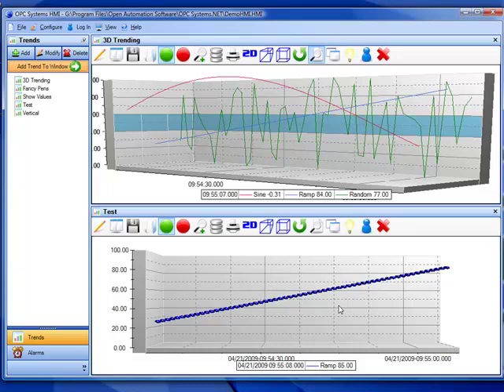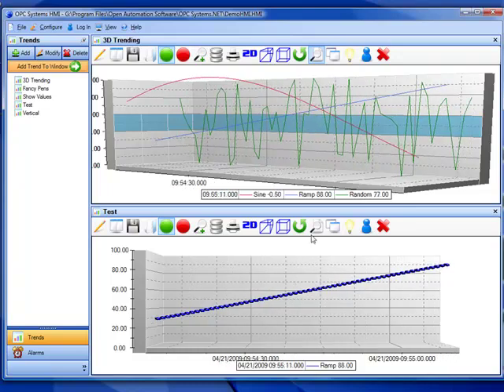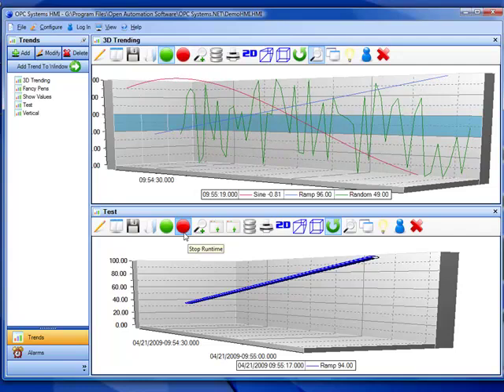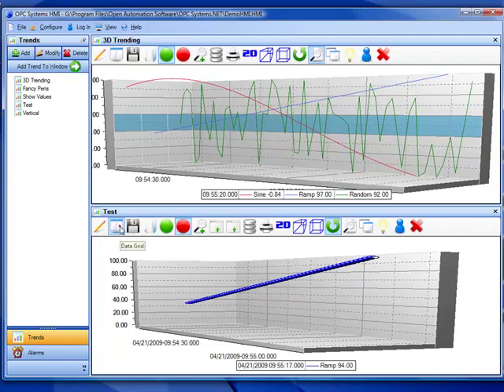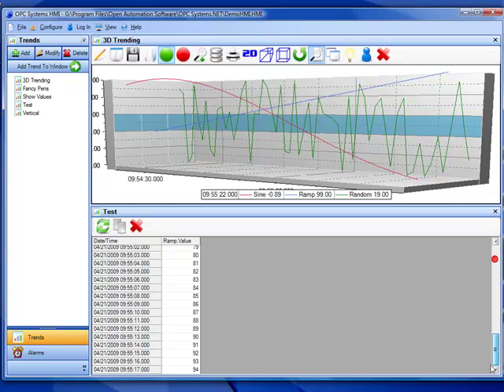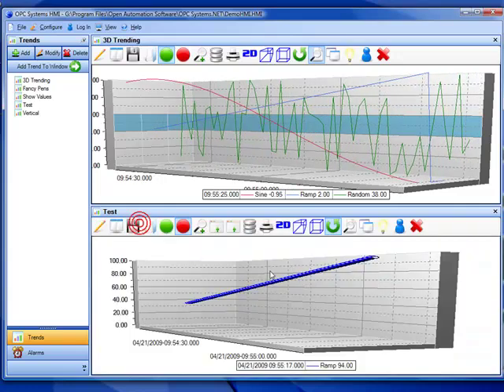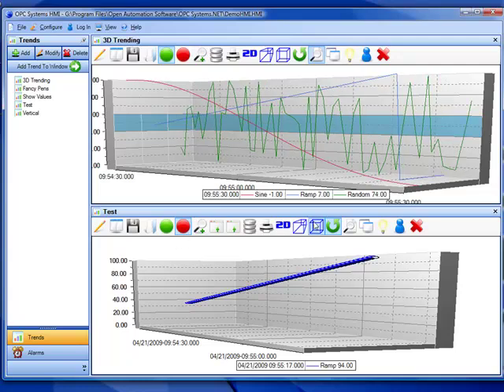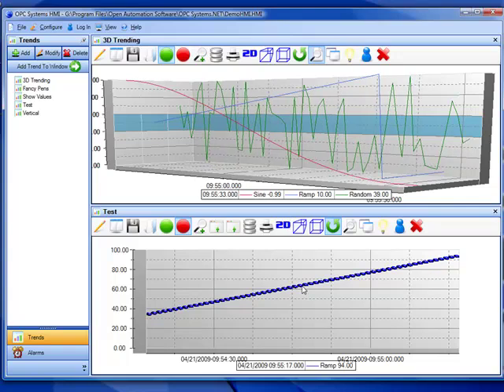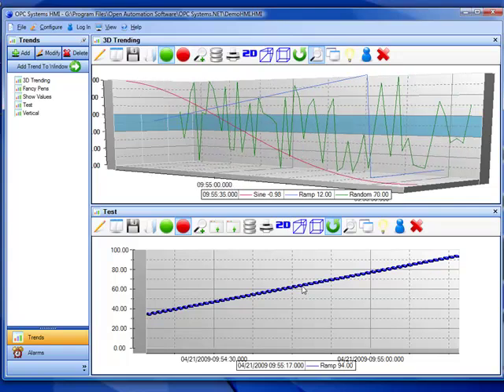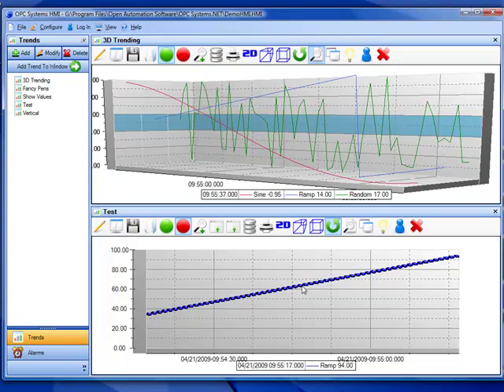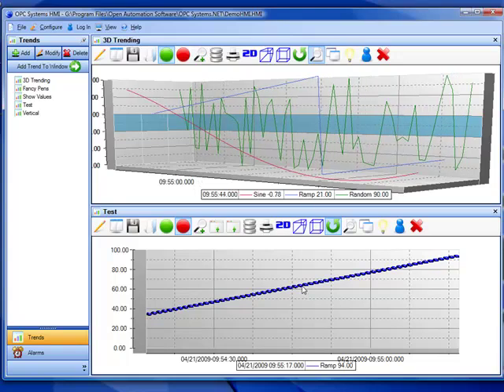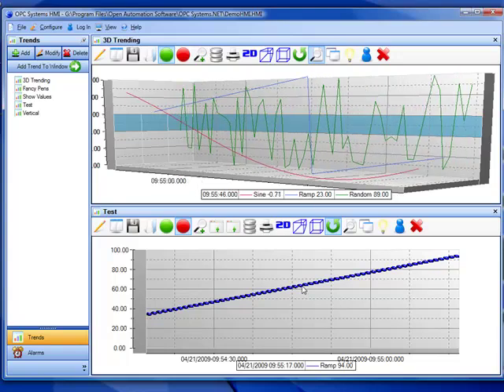We can then rotate the trend, analyze, and see what the raw values are. You can see that the trend already filled the information in from pre-cached data from the real-time service. This is an important feature of opcsystems.net that provides data buffering, so all trend information, even when you're communicating across the internet, is made available and you don't lose any of your data on a temporary network connection loss.